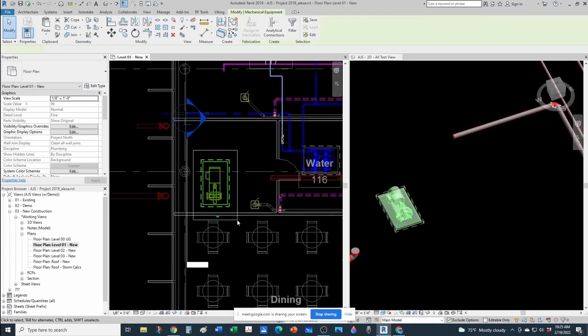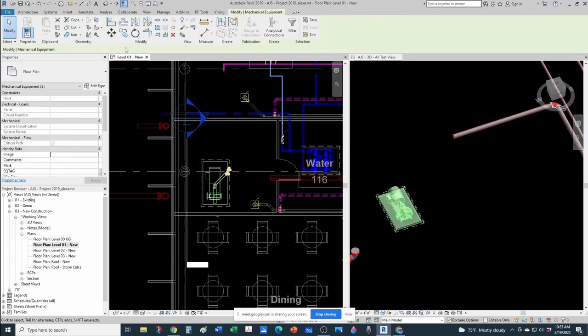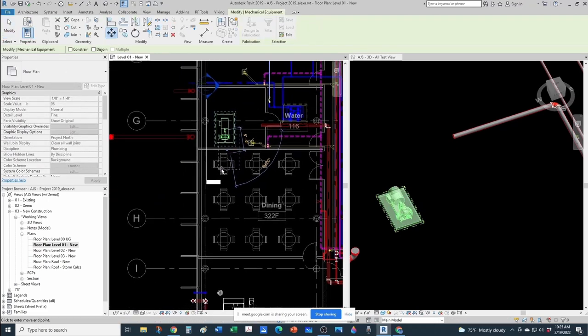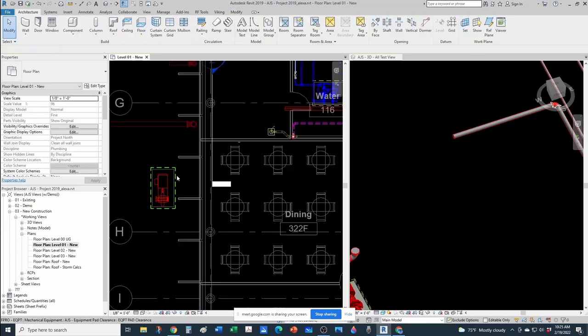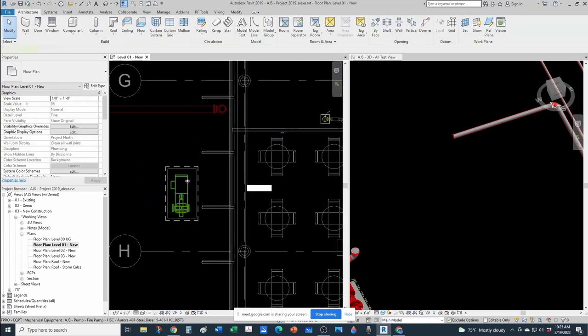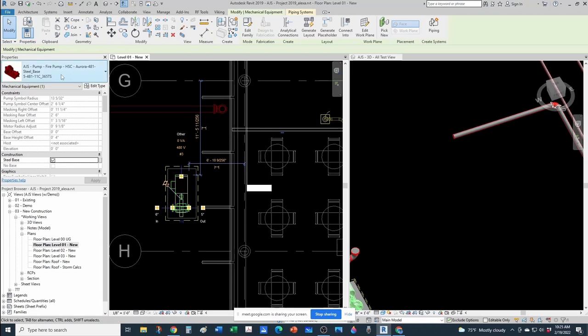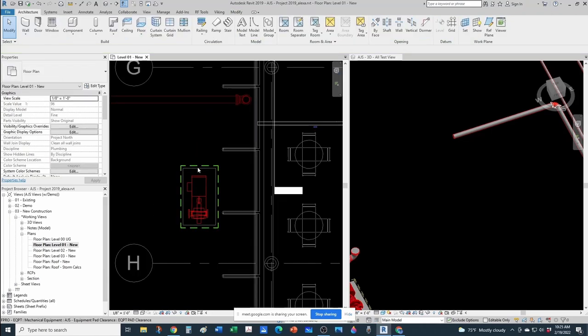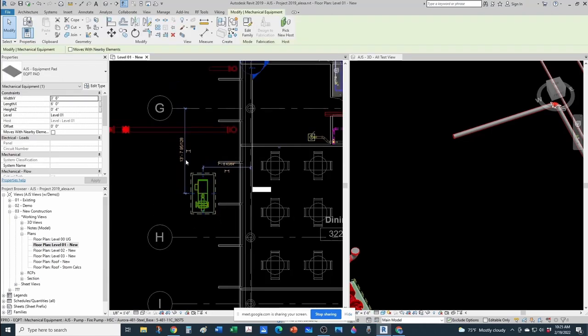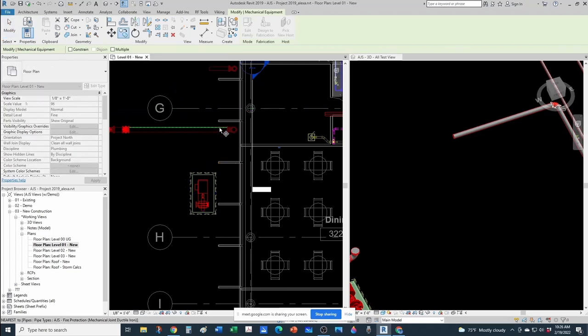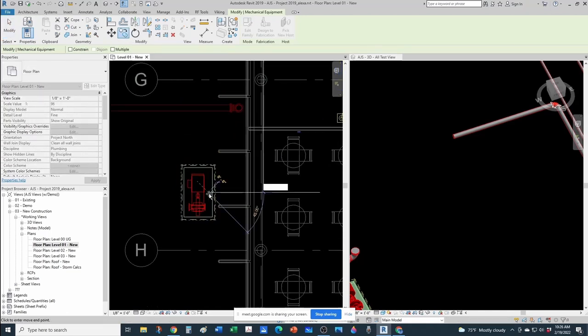Okay, so the first thing you would want to do is to obviously select your fire pump. And in this case, I have an Aurora pump. Aurora Pentair is a horizontal split case pump, series 481. But any of your preferred manufacturers would do. Peerless, Patterson, AC Pumps, Armstrong, all good manufacturers, as long as it's FM approved and UL listed. Let's provide a housekeeping pad first, typically 6 inches in height, so you can level your pump and keep it out of flooding.